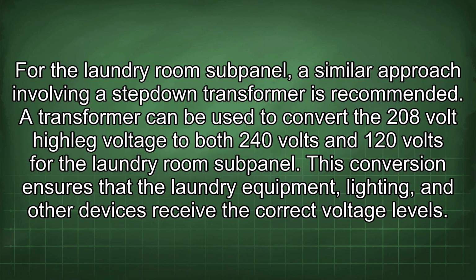For the laundry room subpanel, a similar approach involving a step-down transformer is recommended. A transformer can be used to convert the 208-volt Highleg voltage to both 240 volts and 120 volts for the laundry room subpanel. This conversion ensures that the laundry equipment, lighting, and other devices receive the correct voltage levels.